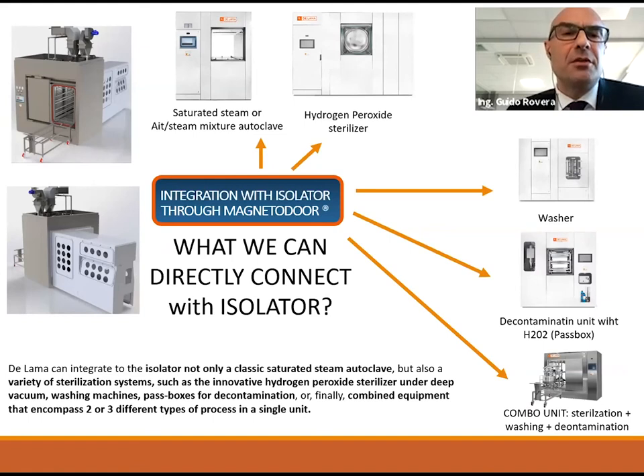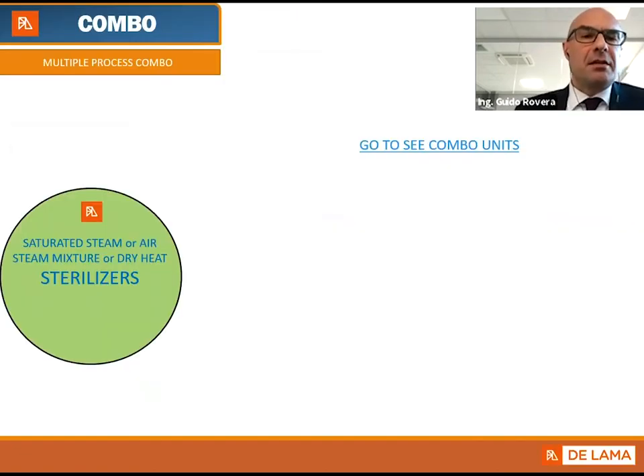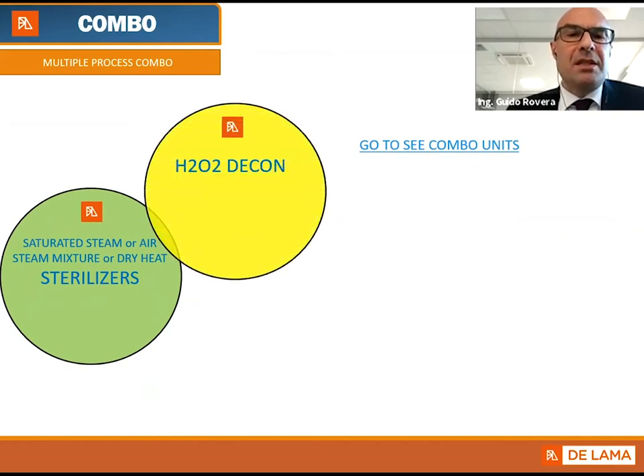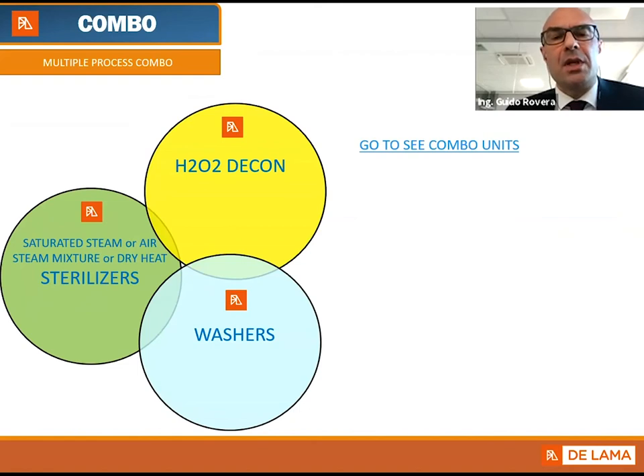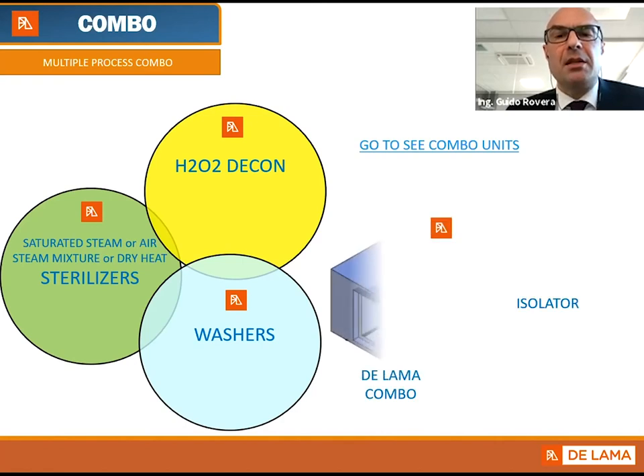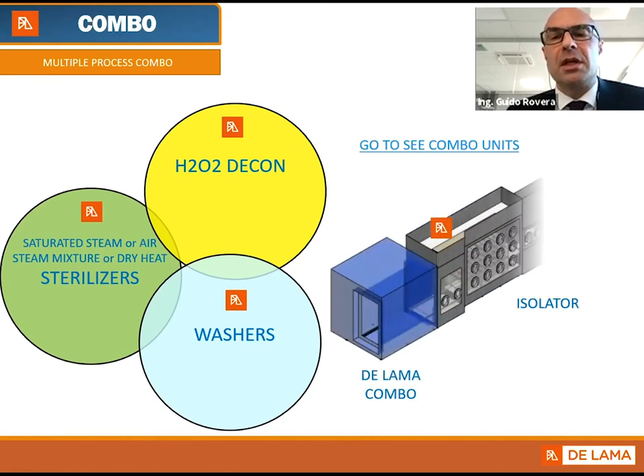Then whatever unit can be integrated with whatever type of isolator using the technology of the magnetically driven sliding doors. So to summarize, we have a sterilizer that can be whatever type. We also master the hydrogen peroxide technique, either in decontamination or sterilization mode, and we master the technique of washing. These three techniques can be either combined together or used in standalone mode, and they can be integrated into the isolator.